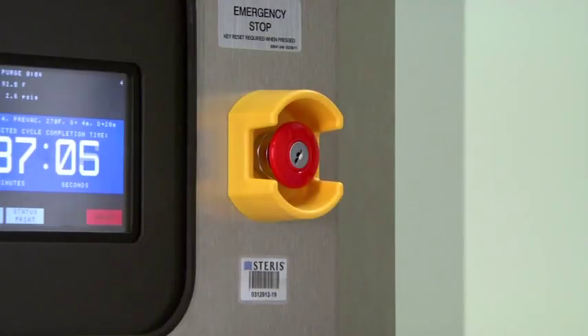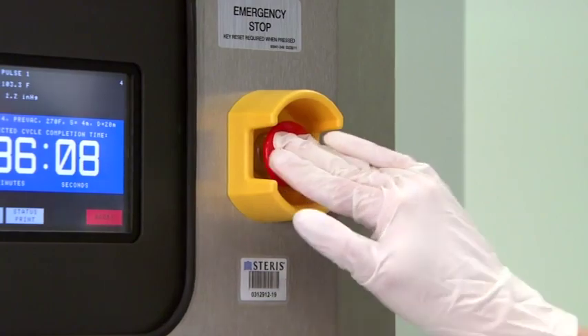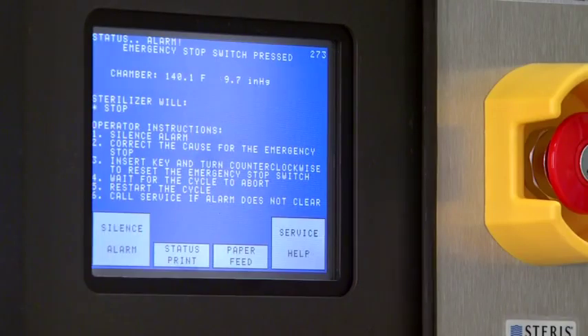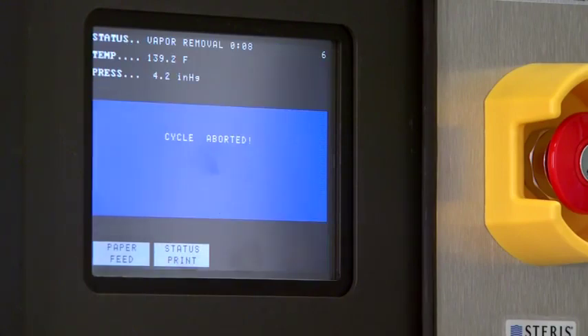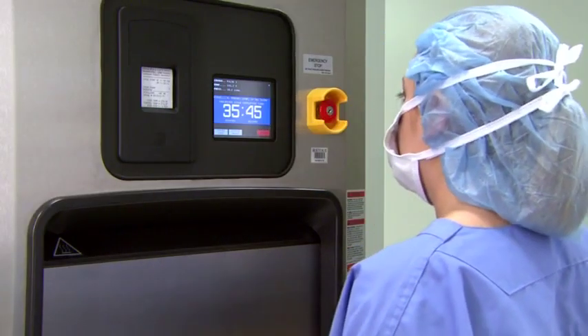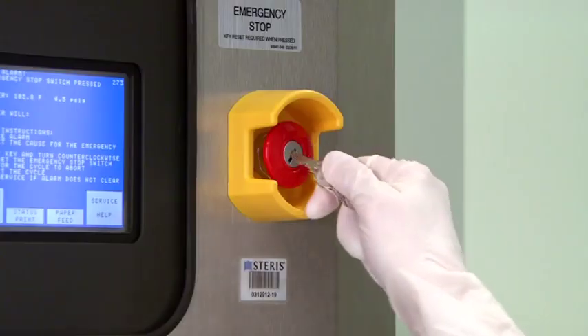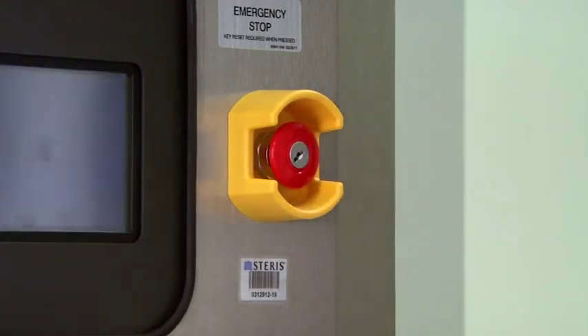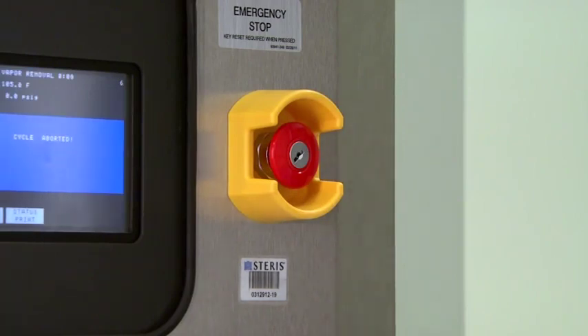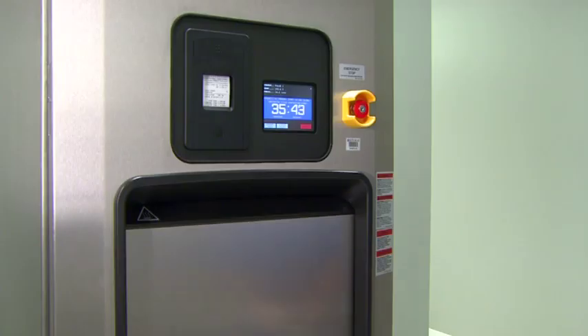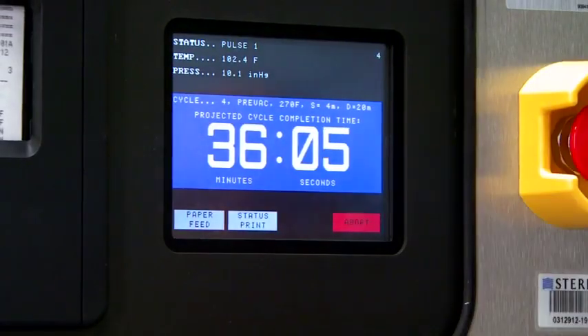An important safety feature to note is the emergency stop switch. This feature shuts the sterilizer down completely in an emergency situation. Pressing the emergency stop switch disconnects power to the door and valves, causing the door to stop and critical valves to close. An alarm is generated when the emergency stop switch is pressed. An emergency stop key is required to reset the switch. Refer to the alarm procedure in the operator manual to clear the alarm. Do not use the emergency stop switch as a start-stop switch. To properly abort a cycle, press the Abort button on the sterilizer display.